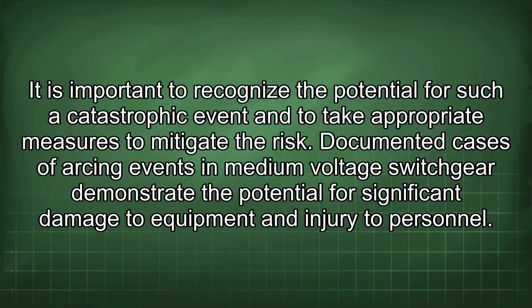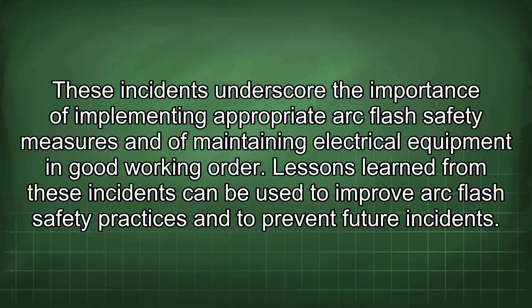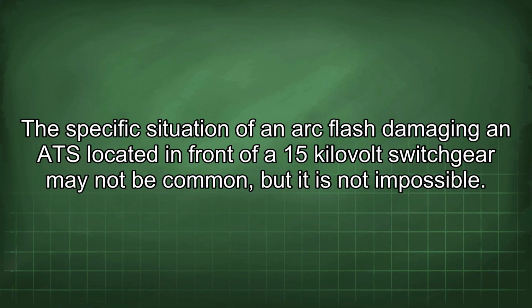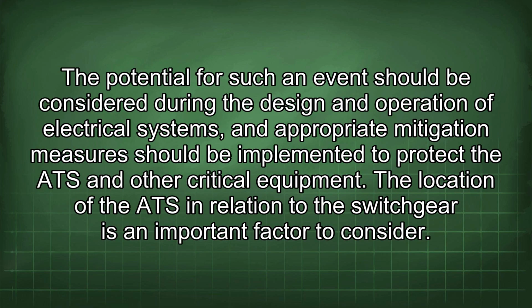risk. Documented cases of arcing events in medium voltage switchgear demonstrate the potential for significant damage to equipment and injury to personnel. These incidents underscore the importance of implementing appropriate arc flash safety measures and of maintaining electrical equipment in good working order. Lessons learned from these incidents can be used to improve arc flash safety practices and to prevent future incidents. The specific situation of an arc flash damaging an ATS located in front of a 15 kilovolt switchgear may not be common, but it is not impossible. The potential for such an event should be considered during the design and operation of electrical systems, and appropriate mitigation measures should be implemented to protect the ATS and other critical equipment.